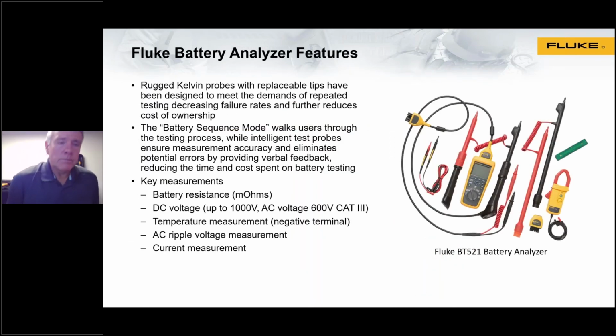Now we'll take a look at the battery analyzers themselves. The Fluke BT521 battery analyzer is our most complete kit. It has the replaceable Kelvin probes for the 4-wire measurements. The tool has something called the battery sequence mode, which we'll look at further. It makes it very straightforward for operators to walk through the testing process, make their measurements, automatically capture the measurements, and then save them in the tool for automatic report generation. So it saves a lot of time. You don't need to write anything down as you're walking around performing your routine measurements.